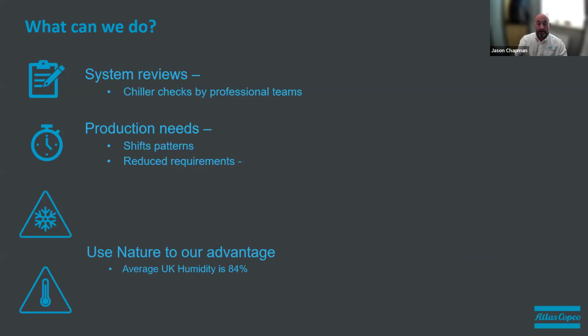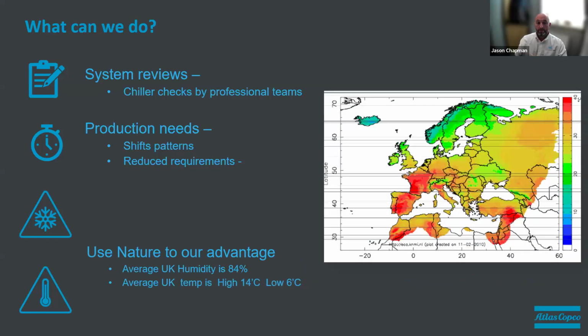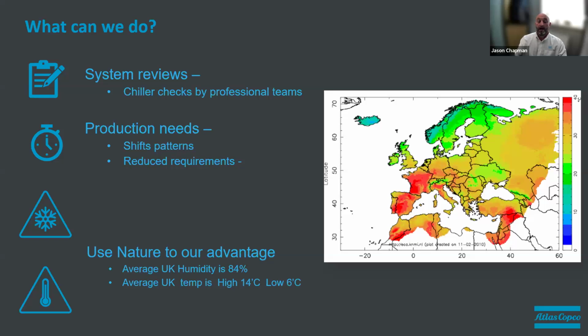But what else can we look at? And within the UK, we need to look at the temperatures. The average UK high annually is 14 degrees. Yeah, we get a couple of months where that goes above, where we've got to look at the type of chiller system that we're using or how we use it. But for the rest of the 10 months out of the year, potentially we can use nature to our advantage, and nature's free. We don't have to do anything, it's just there, and we can just make the benefits of it. So what does that lead us into?